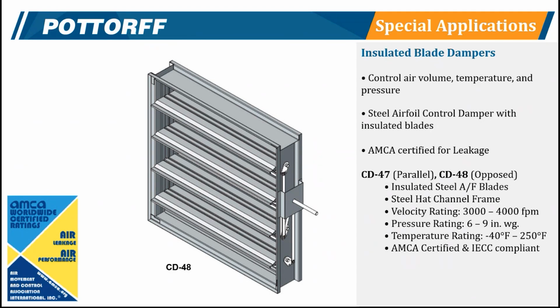Say if an engineer specifies it, there's a Greenheck model that crosses to this that we'd pretty much use as the basis, but it does have AMCA certified leakage, so you'll be IECC compliant for your exterior dampers this way. That's one of the main reasons why we went with the CD-47 and CD-48 compared to, say, the Ruskin option, which is blade insulation on a triple V damper, as it gives you that increased performance and you still have that AMCA certified leakage to meet the IECC compliant exterior damper requirement for energy conservation.